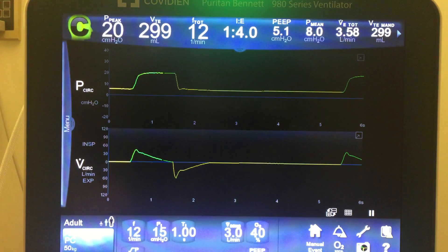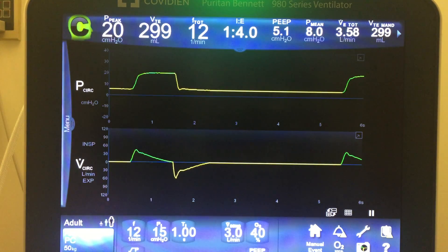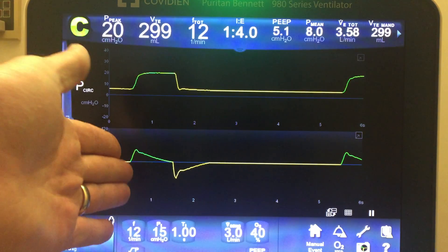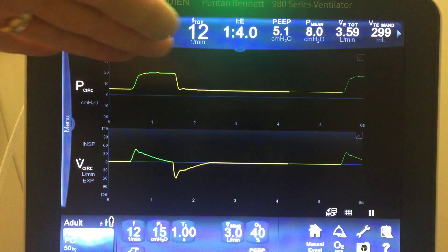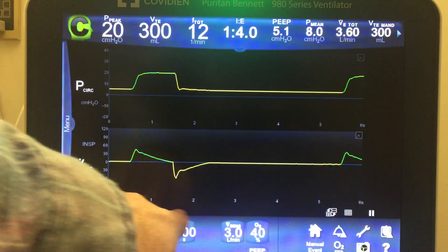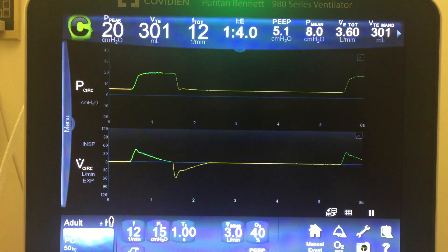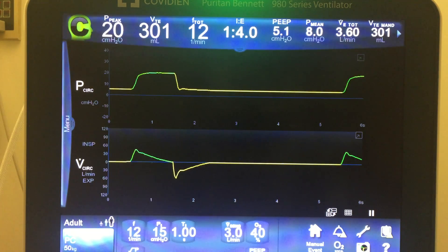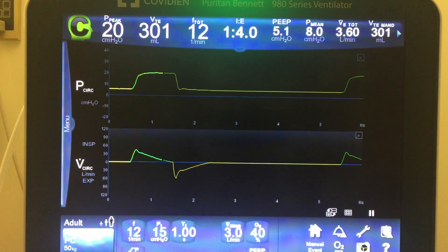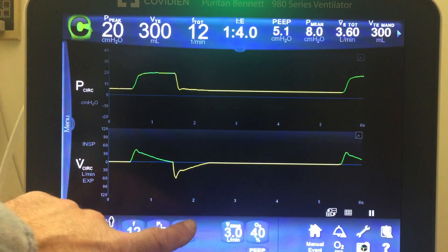Let's talk about the breath again. The flow goes in — we don't control the flow at all. It's predetermined by the manufacturer, but flow goes in until the pressure is met, and then it holds that pressure for the preset I-time. Changing the I-time in pressure control does not change the flow. It just changes how long the breath is held until it is allowed to go into exhalation. So it is pressure limited, time cycled.